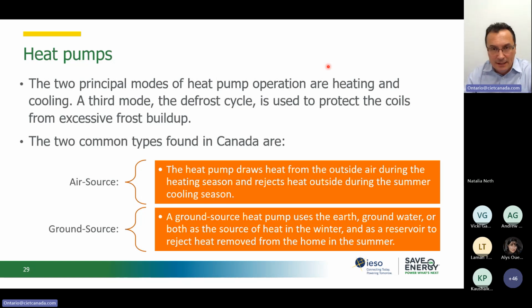So all this is part of the analysis, and I'll show you the impact on the efficiency of the pump in a couple of slides. Now, I mentioned air source heat pumps because these seem to be how the industry is evolving very quickly now. We have a lot more research done to make these heat pumps efficient at low temperatures. There are heat pumps that are designed to operate reasonably at negative 25 degrees Celsius, which is covering pretty much all year heating season in our climate zone.